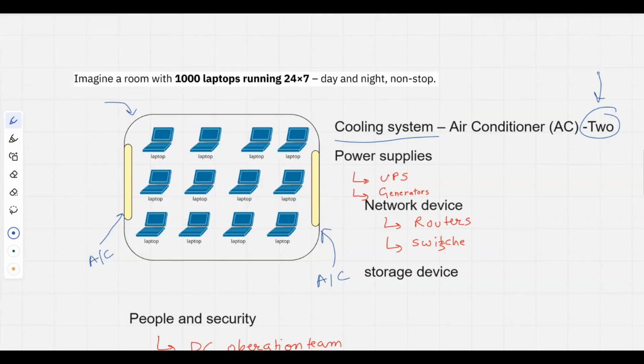So if one power supply line fails, the second one keeps it running. Not only that, besides the two power supplies, we also configure UPS systems and generators, and we put two of those as well. If one fails, we have an alternative. The UPS handles short outages, say 5 minutes or 2 minutes, and the generator handles longer power cuts when the outage is longer.